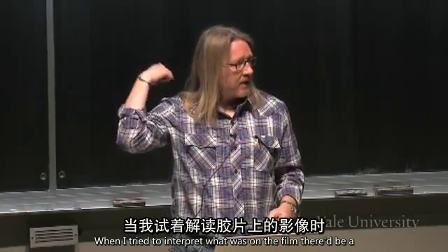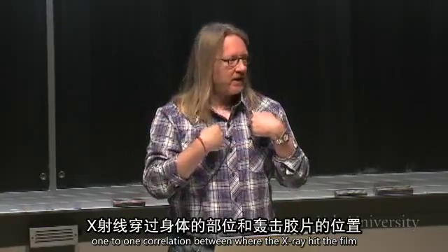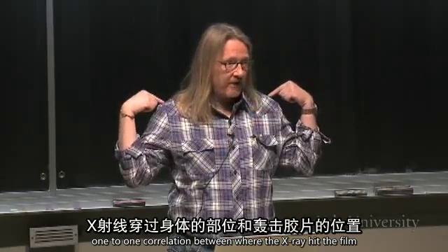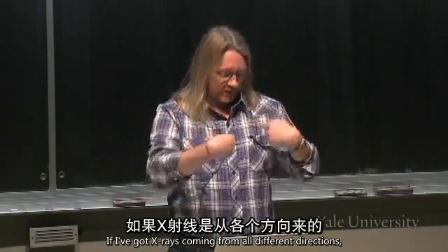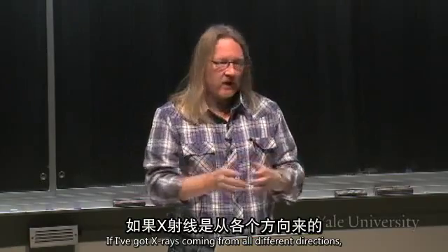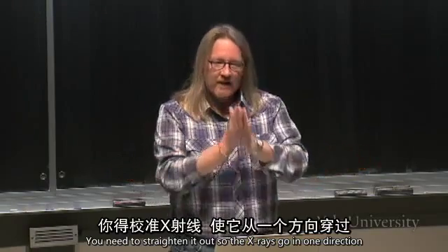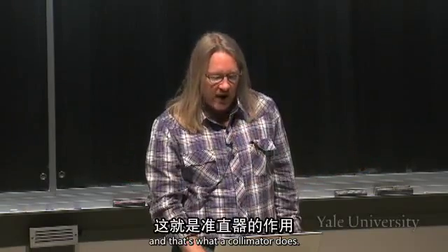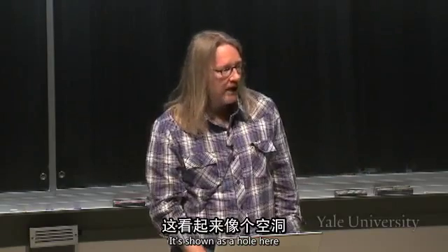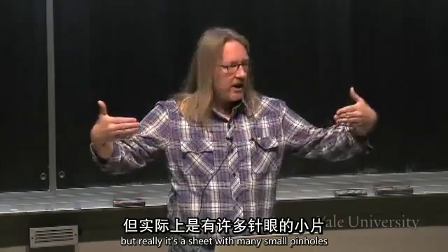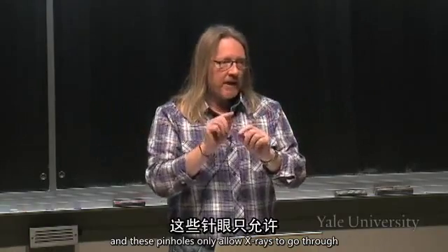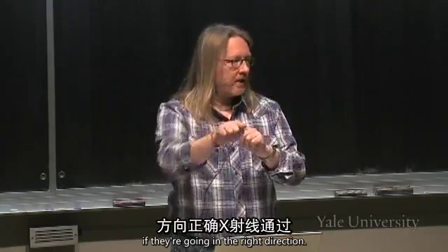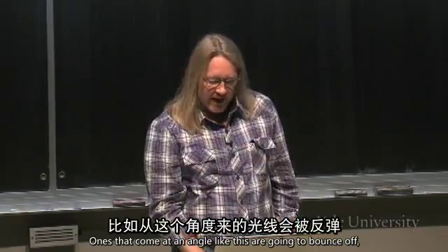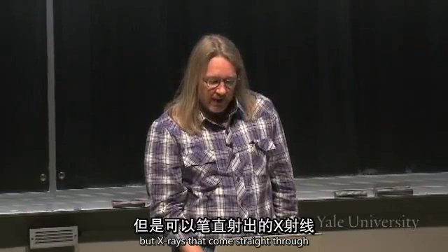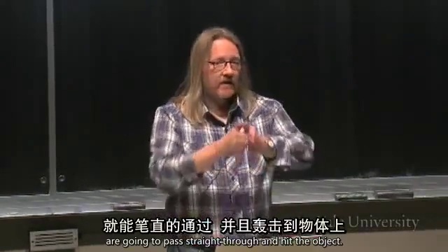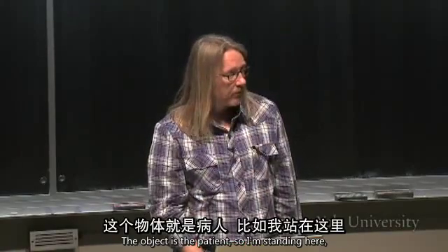So that when I tried to interpret what was on the film, there'd be a one-to-one correlation between where the X-ray hit the film and where it went through my body. If I've got X-rays coming from all different directions, then that's going to blur the image, right? So you need to straighten it out so the X-rays go in one direction, and that's what a collimator does. It's shown as a hole here, but really it's a sheet with many small pinholes, and these pinholes only allow X-rays to go through if they're going in the right direction. Right? Ones that come at an angle like this are going to bounce off, but X-rays that come straight through are going to pass straight through and hit the object.